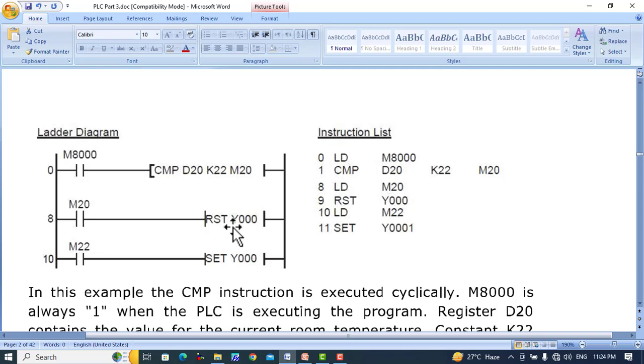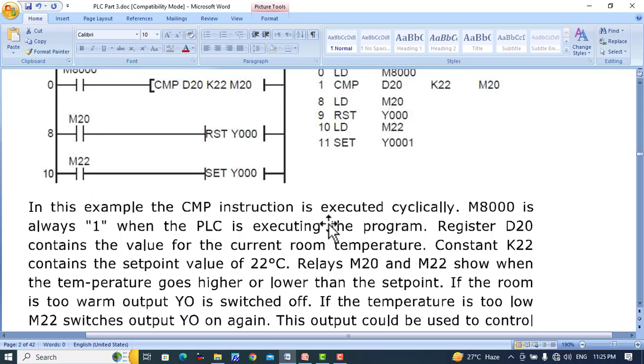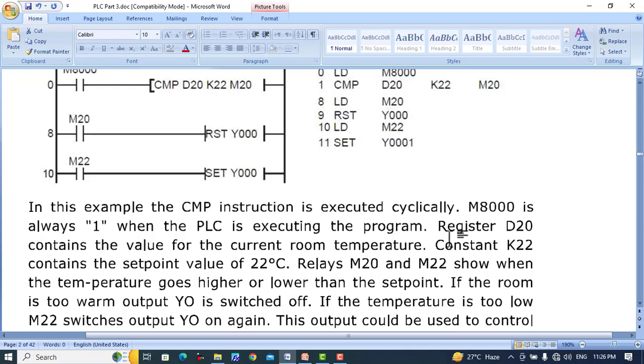When M20 is set to one it will reset Y0, which could be a fan or another output device — turning it off. When M22 is set to one it will turn Y0 on again. The CMP instruction is executed cyclically. D20 contains the value for the current room temperature, and constant K22 contains the set point value of 22 degrees centigrade. When the temperature goes higher than 22, M20 turns on and resets Y0. When it goes lower, M22 sets Y0 on again.